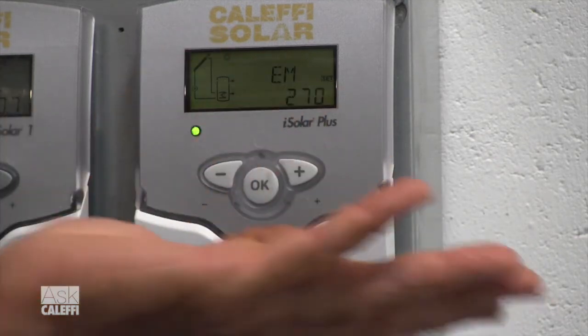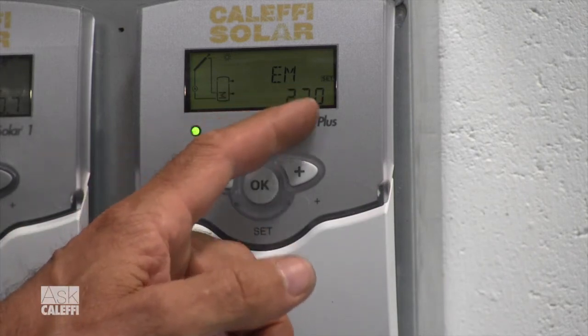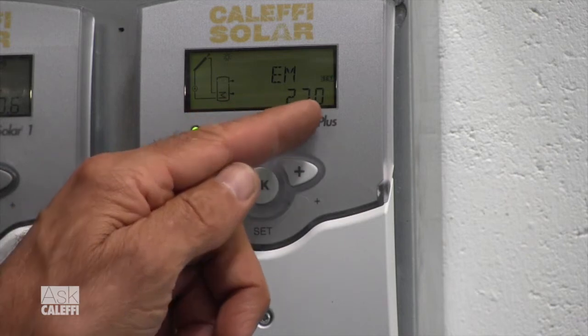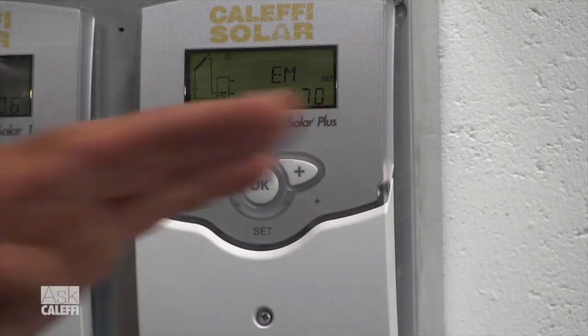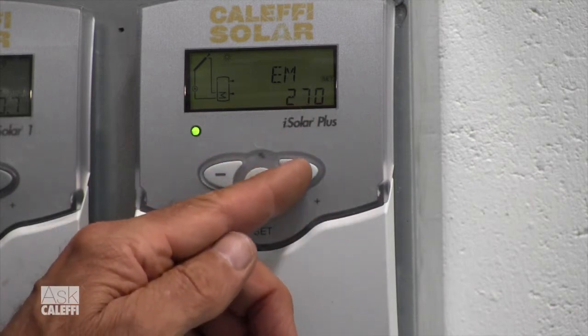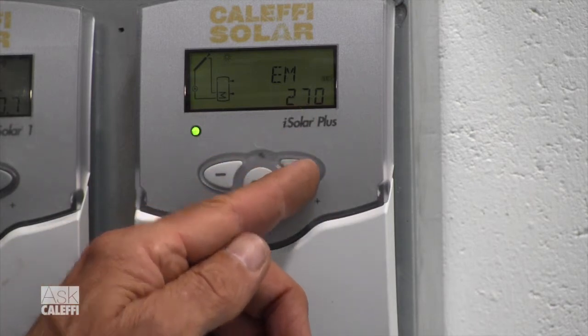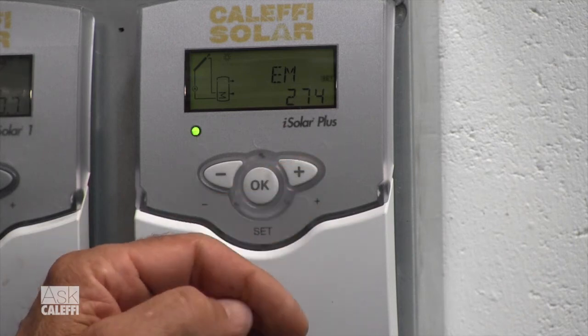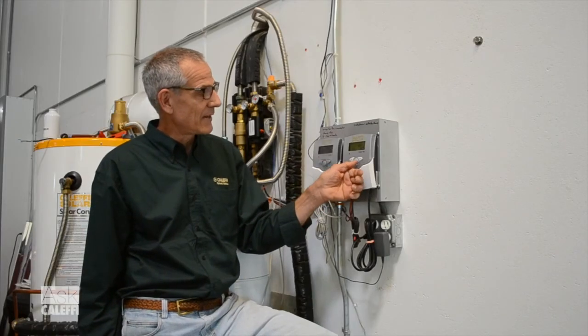The last one in this first setting of Arrangement 1 is EM — emergency shutdown. Once the collector gets to 270 degrees, the pump shuts off and it's not going to run anymore — it's done for the day. That's adjustable. Some people like to bump that up a little higher if you've got good glycol in your system — maybe up to 275.